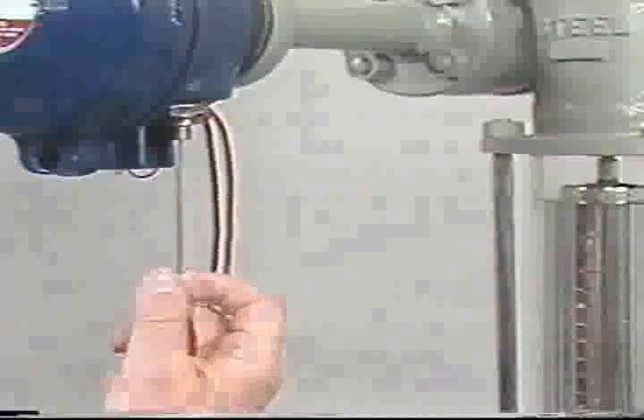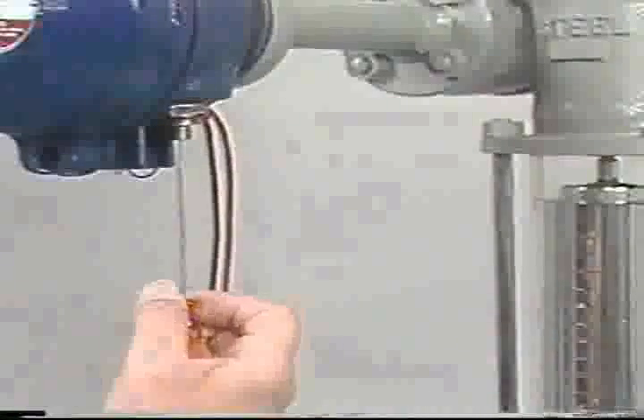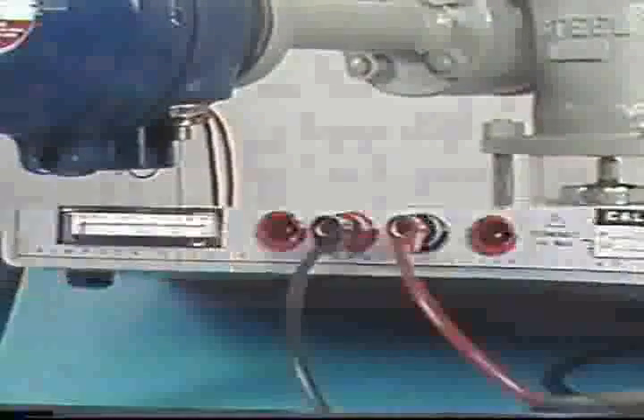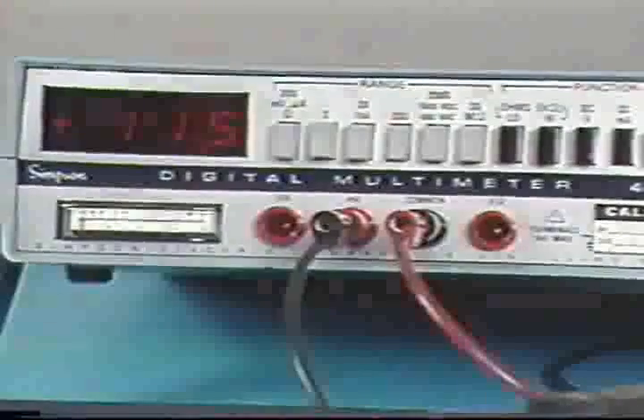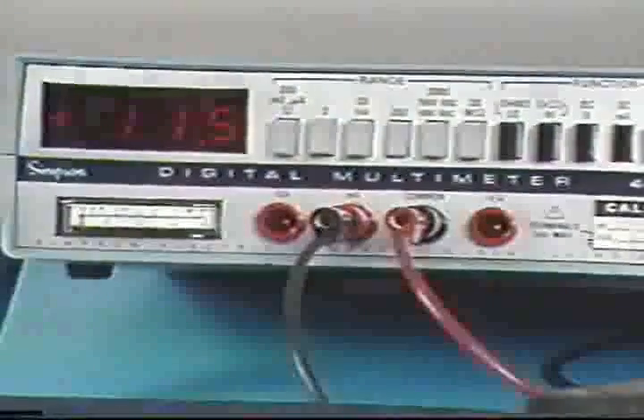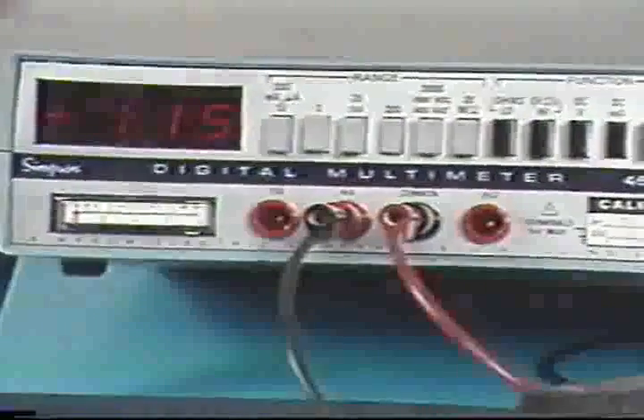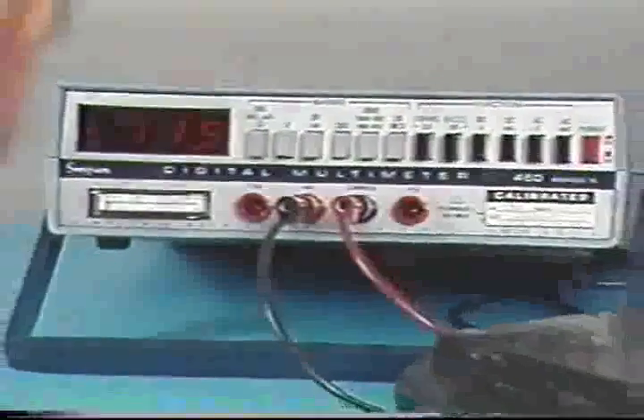Keep checking and adjusting span and zero until they produce the prescribed output. Finally, check and record the output at the mid-range value. Because of the inherent non-linearity of the torque tube spring, linearity is not adjustable on this type of transmitter. You should, however, record the amount of deviation from ideal.